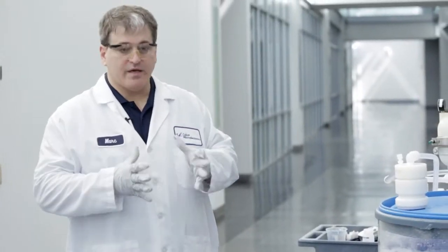Foaming is a concern in slurry for three reasons. The first reason is the foam can pull organic components out of the slurry and retain them, so the materials are not present or not present at the correct concentration in the slurry when it's transferred into the distribution system. This can have an impact on your polishing process and cause variations or issues.